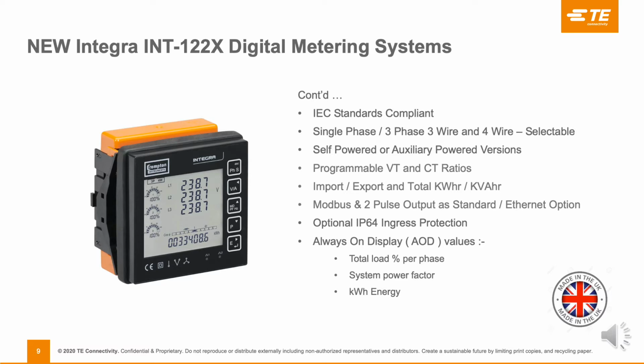In addition to the display, the always on display, the AOD values, does have the load per phase. If you look at the drawing and the picture on the left, it has a display of parameter per phase for the total load. It has a system power factor quick view bar. As you can see in the middle there, the bar is on unity at the minute, at 1, so that's a very quick indication of the power factor, and also has the kilowatt hour energy, which is one of the main parameters, fully displayed all the time.